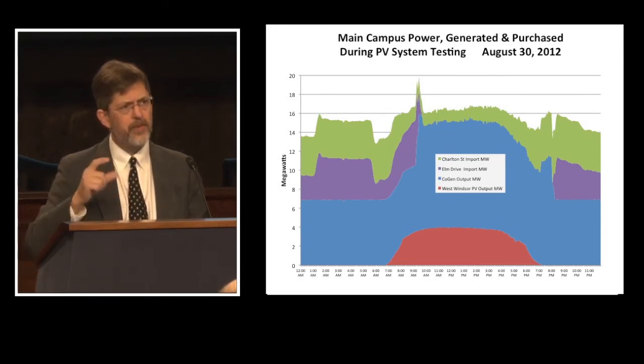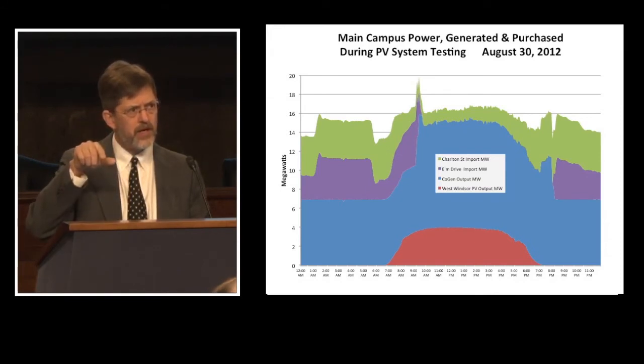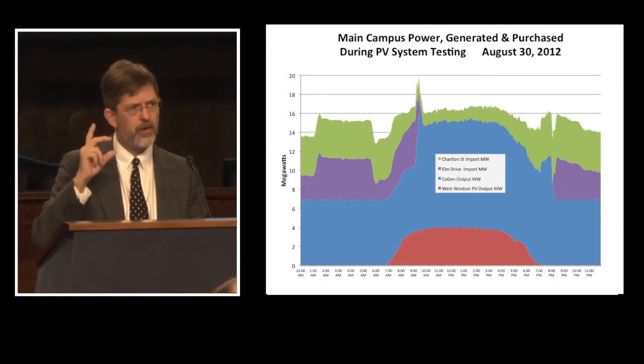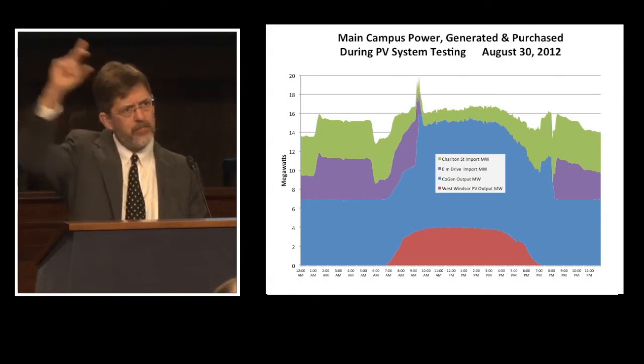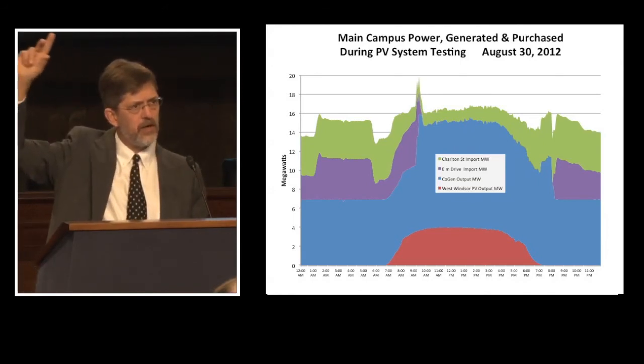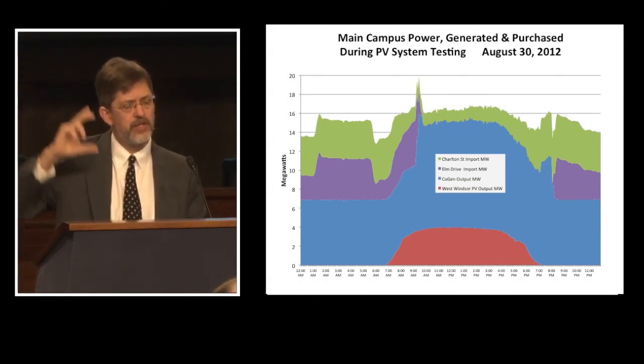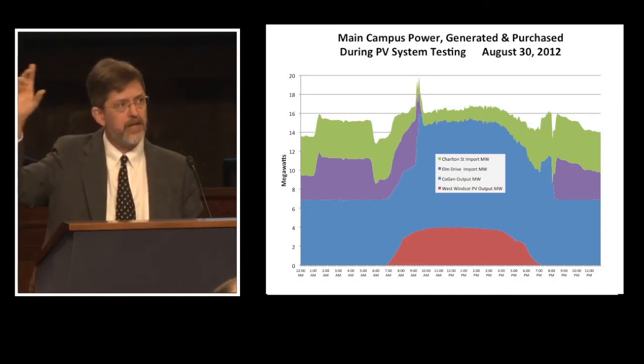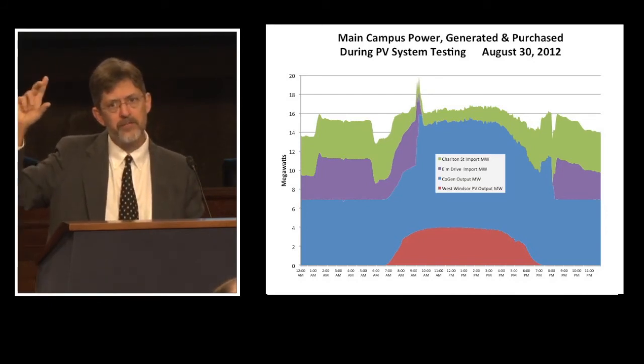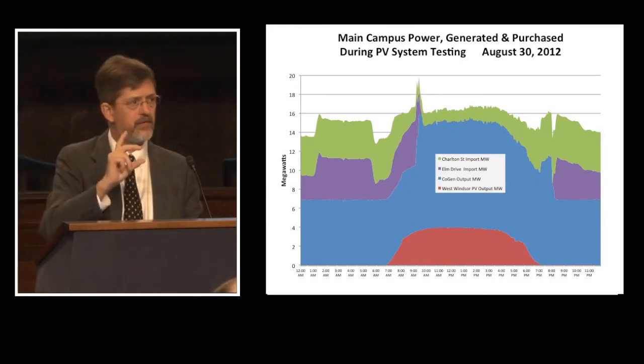The purple is the power purchase on the same substation as that blue cogeneration line. See that rectangle on the left-hand side? That's all the power we bought associated with our thermal storage. Picture that rectangle placed on top of the center of that curve if we hadn't had thermal storage - that's all the power we'd have to buy in the middle of the day, at the most expensive time, when the grid is most stressed.